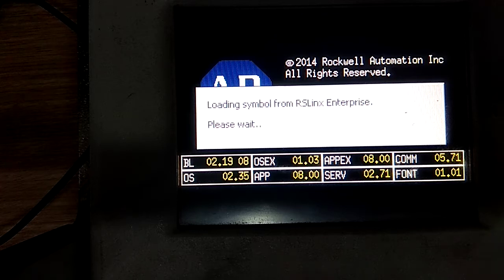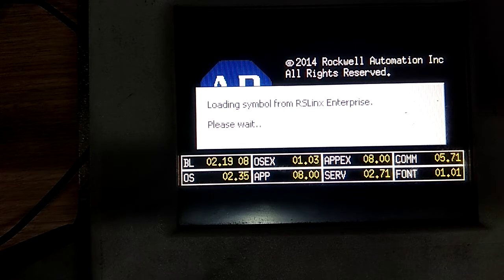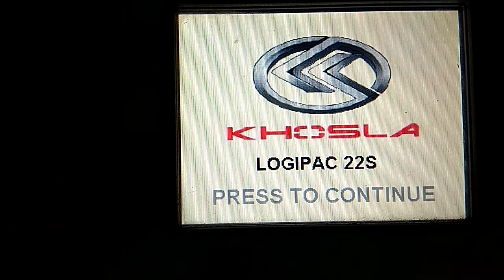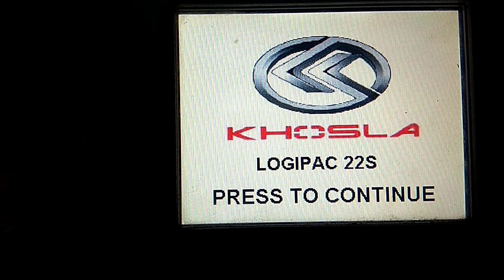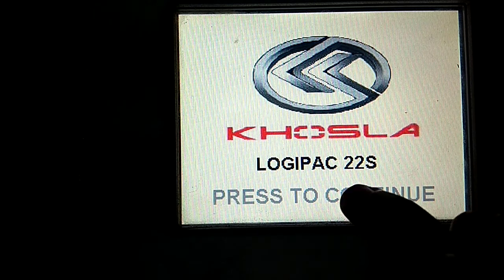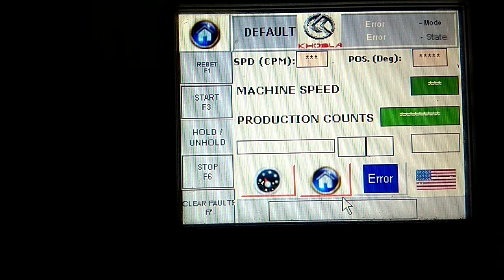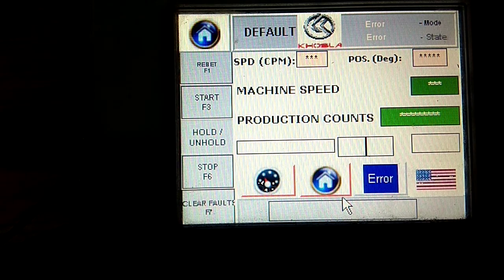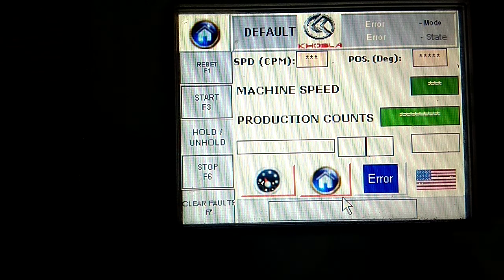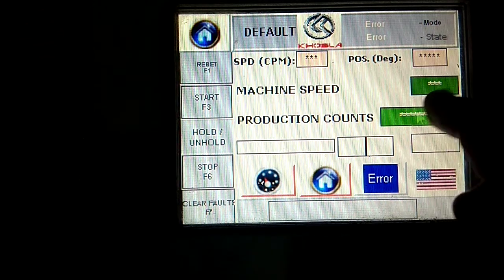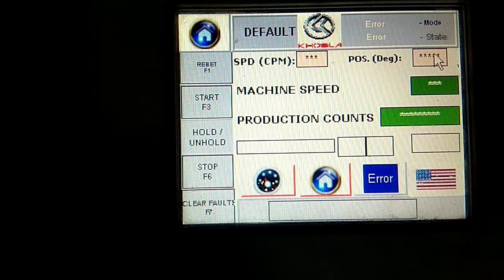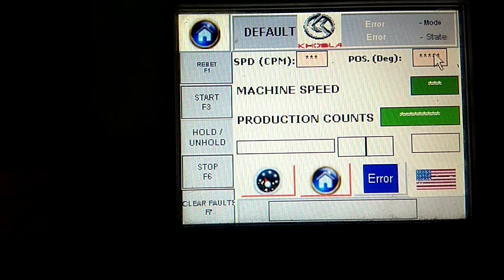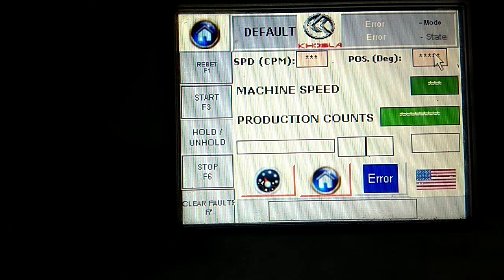So guys, after five minutes of rebooting HMI, see after five minutes of rebooting, it's showing Logipac 22S backup in your HMI. Right now your HMI is showing stars on display - that is an input display and output display. This is the input display and this one is output display. Why is this showing stars on input and output display? Because I am right now not connected with my PLC.